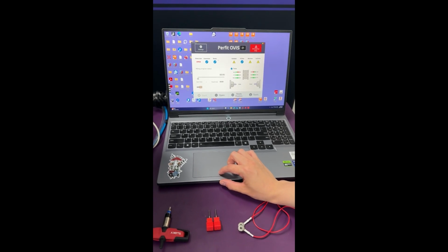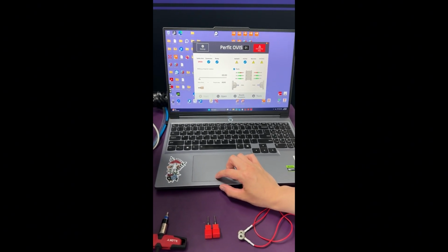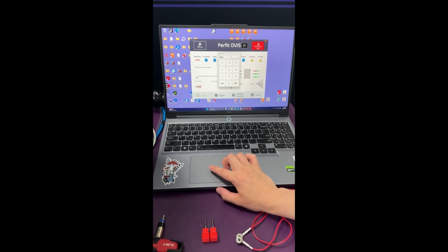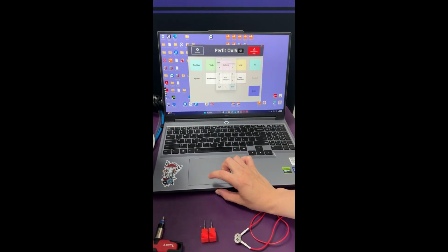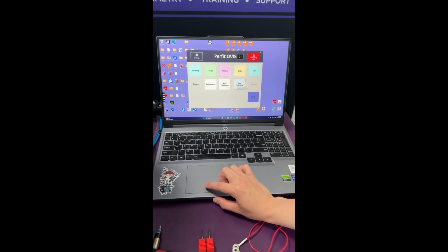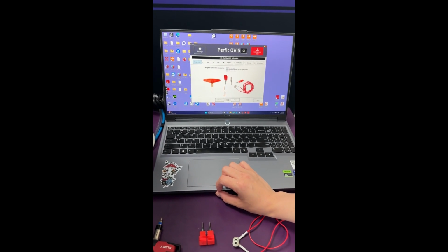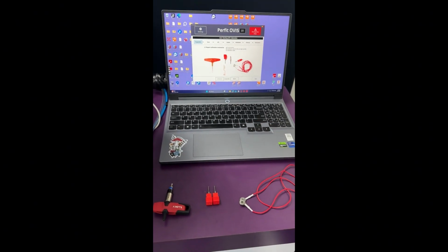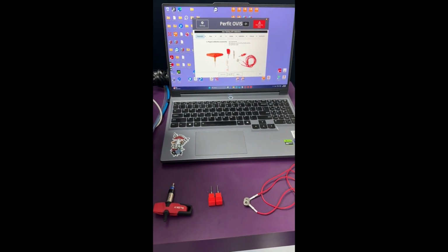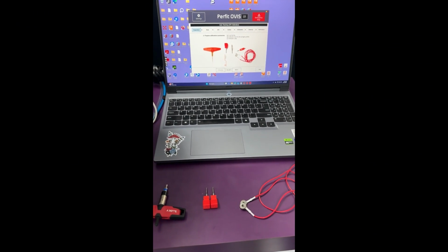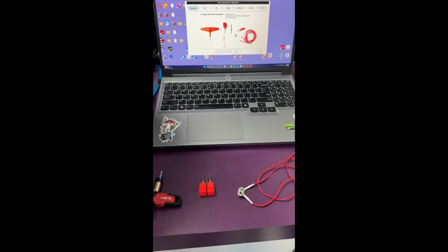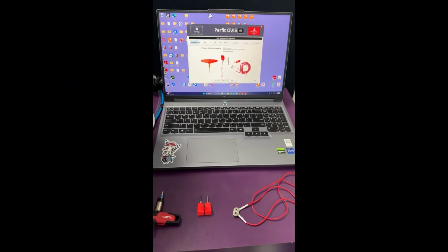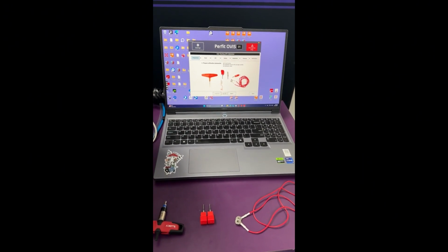Okay, the next thing we're going to do is the auto teaching. So go to the settings menu from the upper left, hit enter to bypass this password, and then click on auto teaching. Very similar to auto calibration, auto teaching is going to have us get our 3mm hex key, our calibration left and right burrs for the spindle here, and then our calibration cable. Once we have those in place, we can click next.